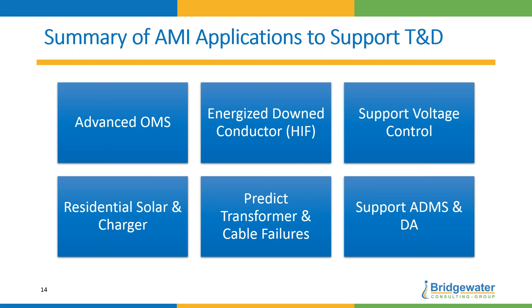So AMI is your new grid sensor. And here's the ABCs - what do they measure? Well, kW delivered, kW received. These are net energy meters that look at power going into a house and power coming out of a house due to solar. Voltage - a very underused component, but the meters do measure voltage.